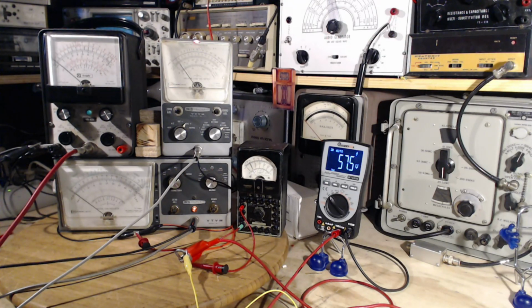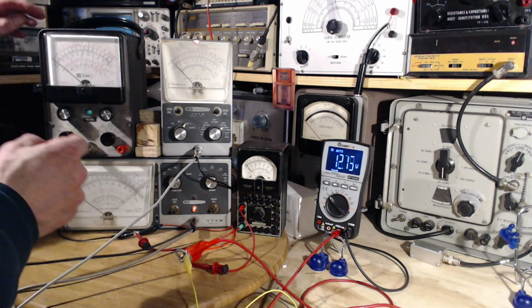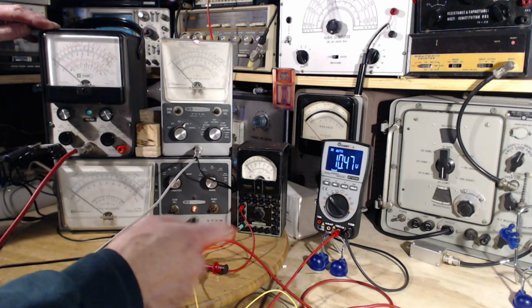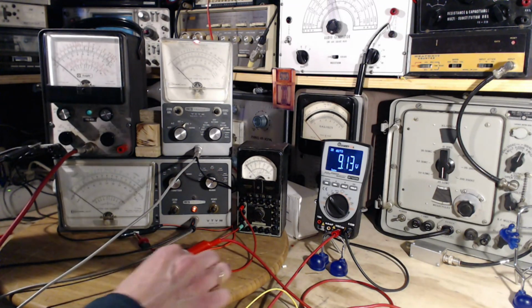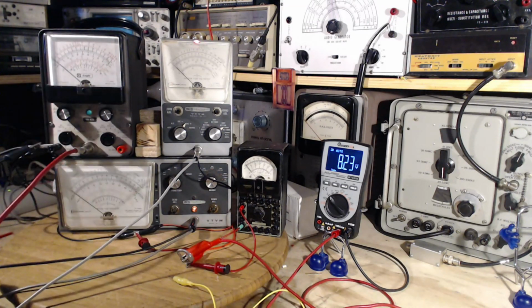Temporarily remove plug, lead plug, set range switch 1.5, function AC, adjust AC balance so no movements detected. Here we are now when you're switching between the three ranges. Set it to 150 and measure 117 volts. So the first thing is set the range at 1.5, function AC. Let's try this meter first. Okay, still got a little bit of voltage here, so let me, well, it's not even connected. It's good. This is just open here.